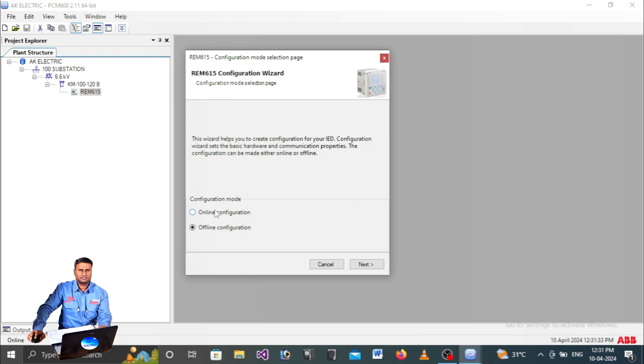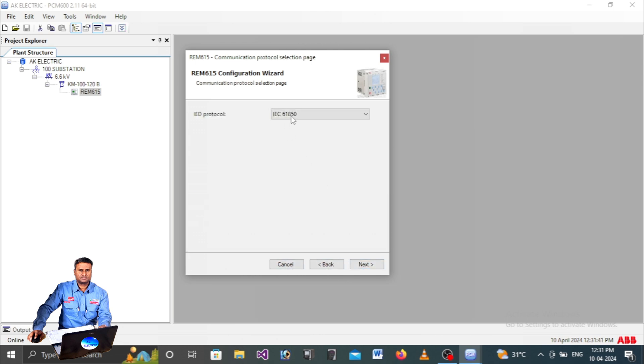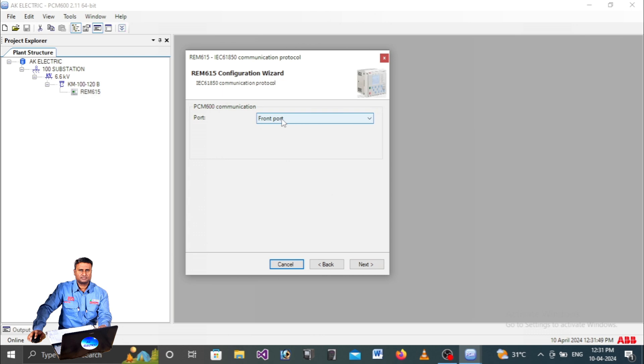There are online and offline configuration options. We are going for online configuration. Click Next, and here IEC 61850 is our protocol, so proceed to Next. You will have two options: front port and rear port (back port). You need to type your IP address - go to the relay and check what the IP address is. In our case the relay IP address is 172.18.150.24.